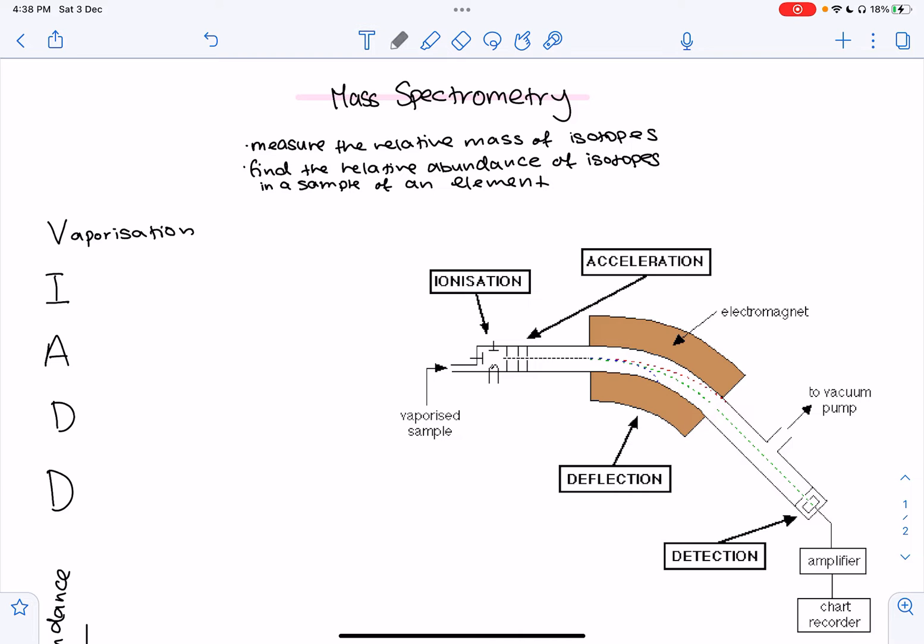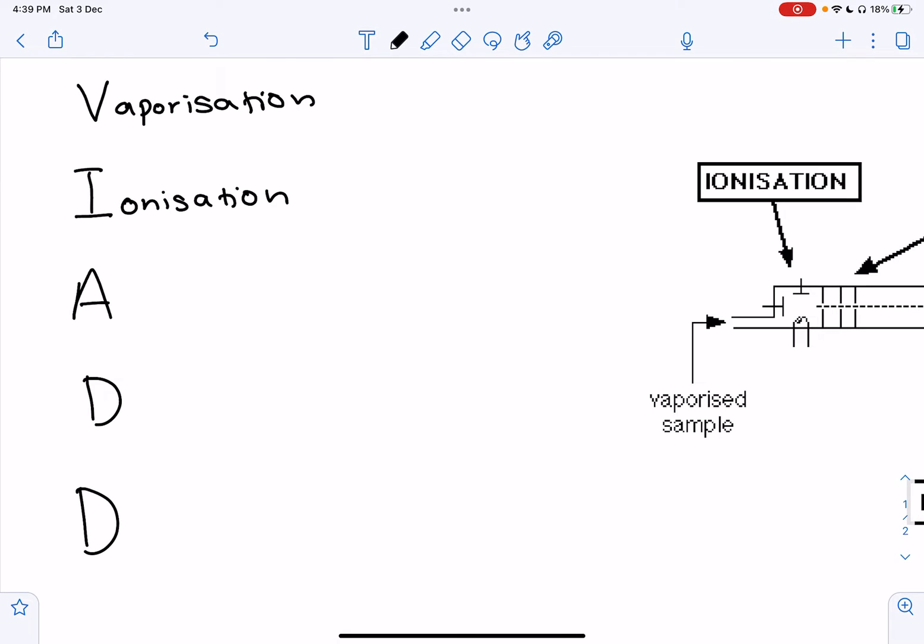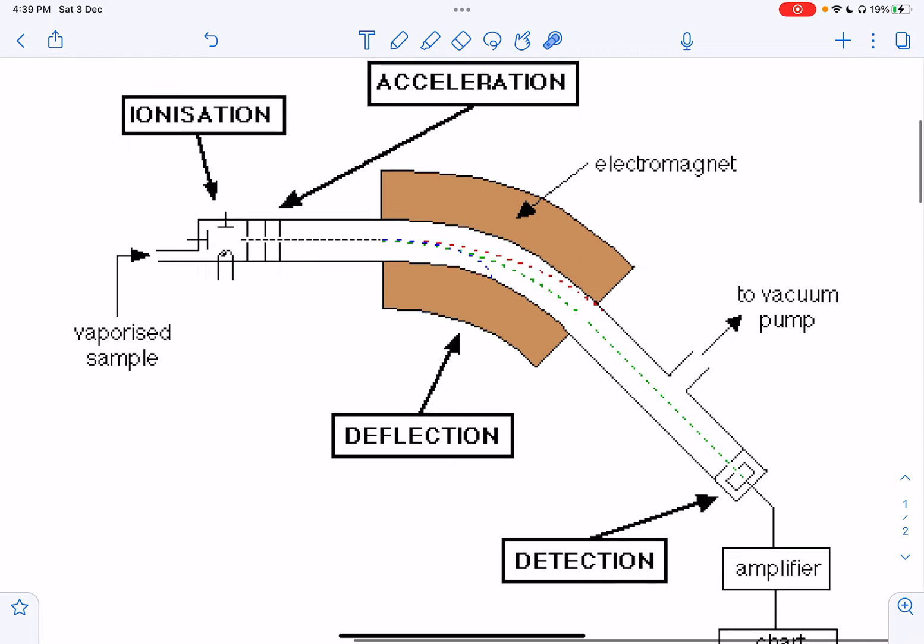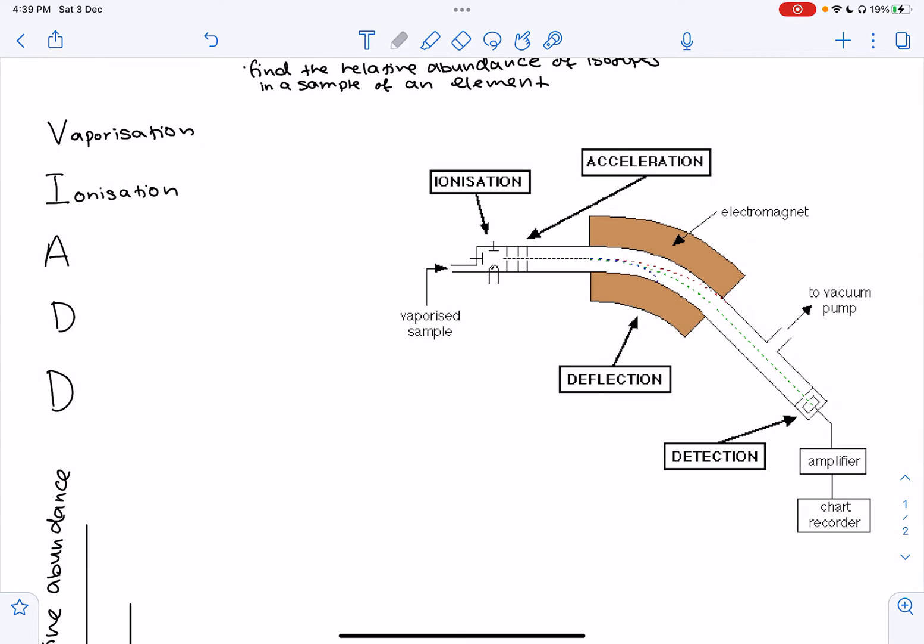The next step is ionization. This is a key step because the sample is bombarded by a stream of electrons emitted by an electrically heated metal coil. The sample is ionized by knocking off one or more electrons to give off positive ions. The atoms are turned into ions and a positive charge is formed. The resulting positive ions then pass through holes in parallel plates under the influence of an electric field where they are accelerated. That's the third step.